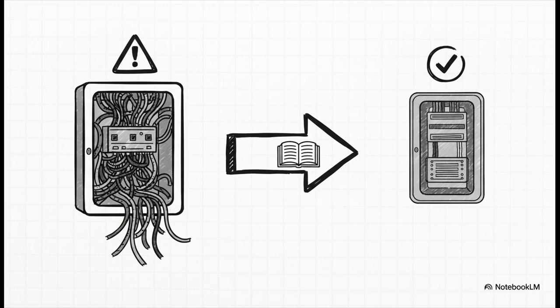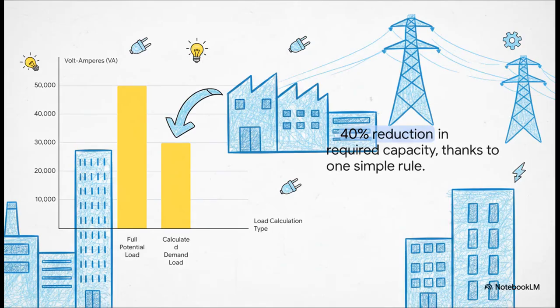And we didn't do it by guessing. We did it by applying a time-tested, data-driven rule straight from the code. Just look at that difference. It's huge. We went from that intimidating potential load of 50,000 VA all the way down to a calculated demand load of 30,000 VA. That is a 40% reduction. You can see right here on this chart just how incredibly impactful this one simple table really is.